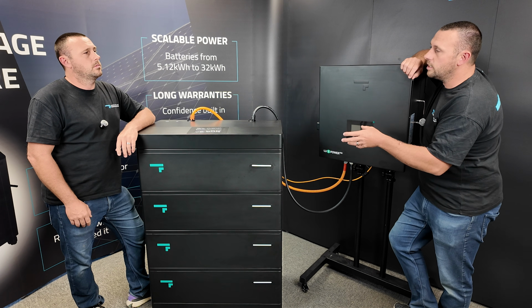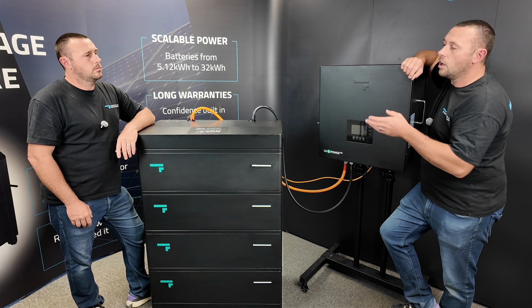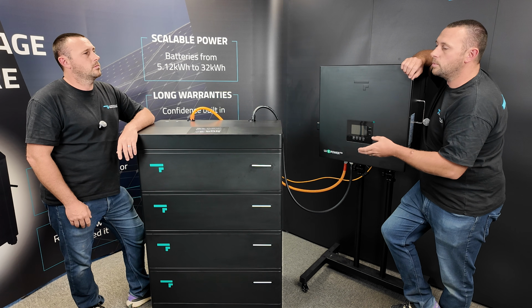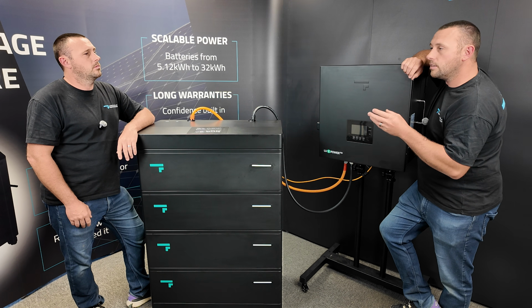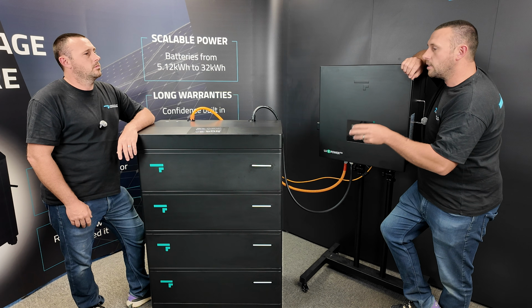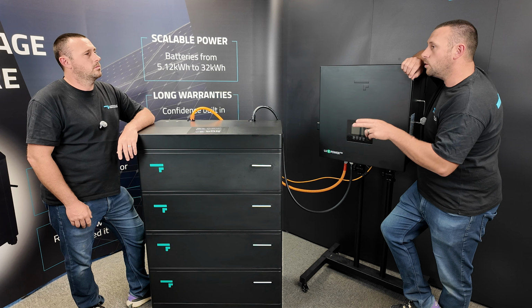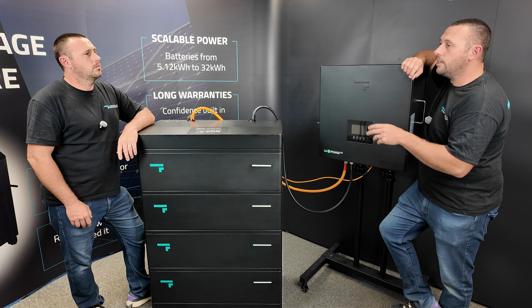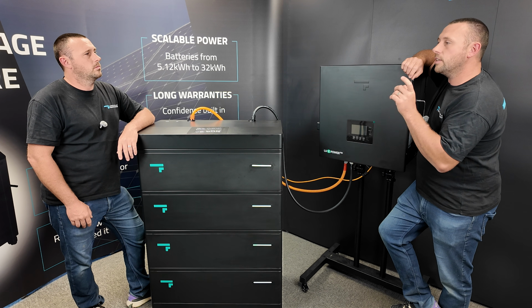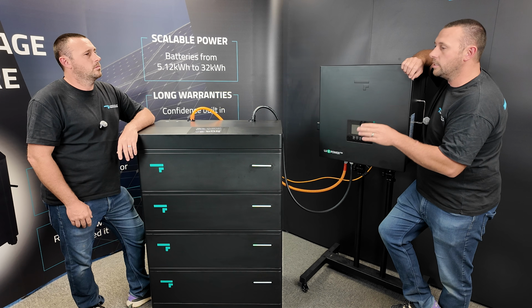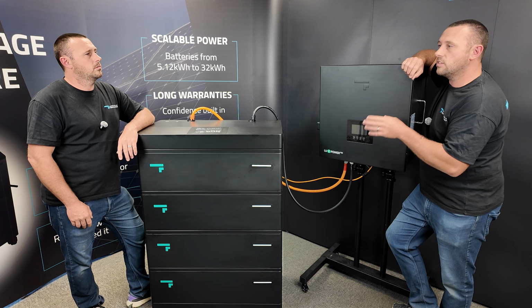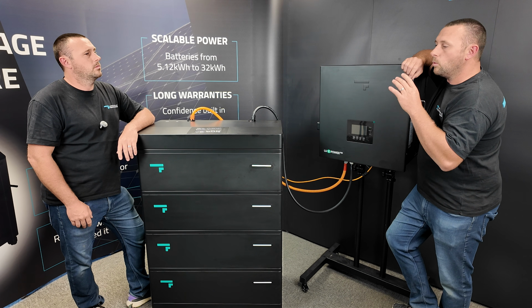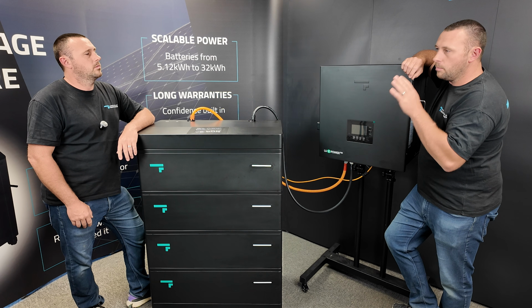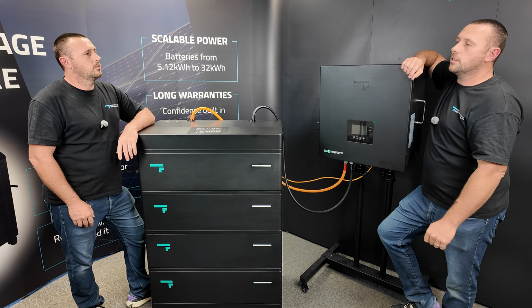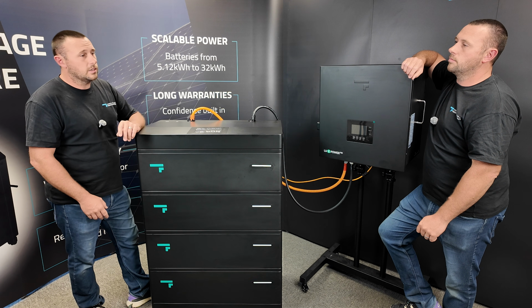Is the battery equipped with any safety features or anything else? Yeah, sure. The battery is equipped with a few safety features. Obviously, each module does have its own BMS. This monitors current and voltages as well as cell balancing to make sure those cells are super happy inside. If for any reason there is an issue, we have an aerosol fire suppression system in there that is triggered at about 170 degrees. So that will cause a chemical reaction with the lithium and put out any potential hazards that might arise.